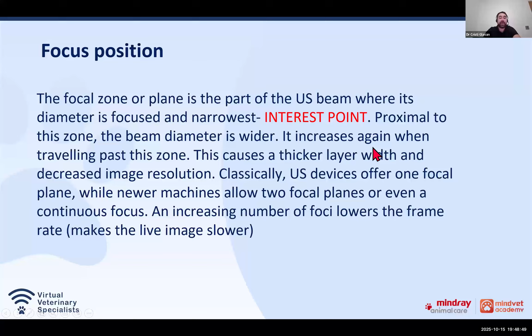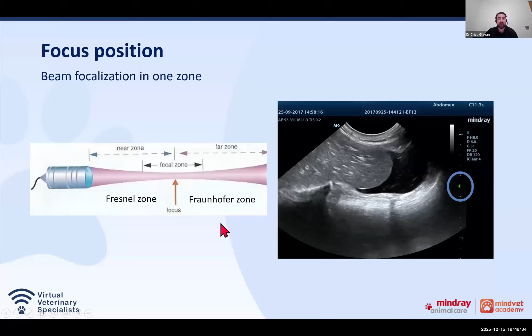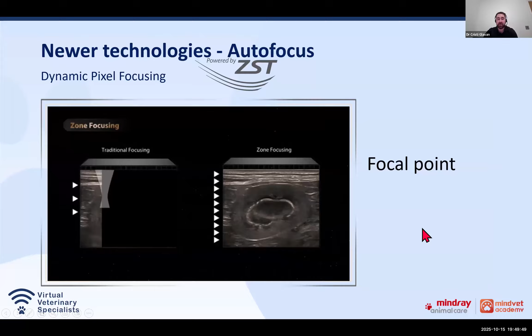So the focal point, depending on the ultrasound machine that we are using, will be presented as a narrow tip or in other shapes, but most of the time you will see it here, presented on the machine. You will have it as a focus point or under different names. That's why I was saying at the beginning that it's really important to know our machine, learn the settings, and check the ultrasound manual of the machine that we are using, so we can make sure that we are seeing those things on our screen and on the machine. Now, different types of machines will have different settings. Some of them, with newer technology, will have autofocus. Everything will be assessed in zones, and we also need to be aware of that. It will improve the image quality and make things faster, so we will not have a single focal point.